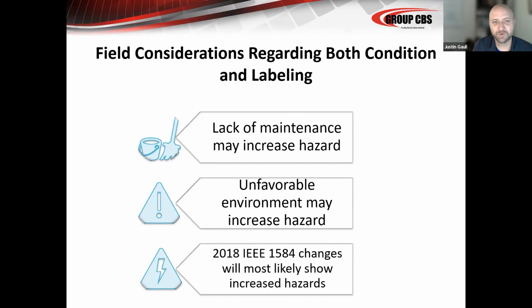For arc flash labels, the label has a working distance and level of PPE at that working distance. It also has the arc flash boundary distance. How do you determine the level of PPE entering the arc flash boundary, but not near the working distance? Okay, so the reason that there's an arc flash boundary is that at that boundary distance, like the one that was 112 inches that I showed, without PPE you are at risk of a second degree burn. So that arc flash boundary is the indicator that anything past that boundary, you need to be wearing PPE. The working distance is generally 18 inches.